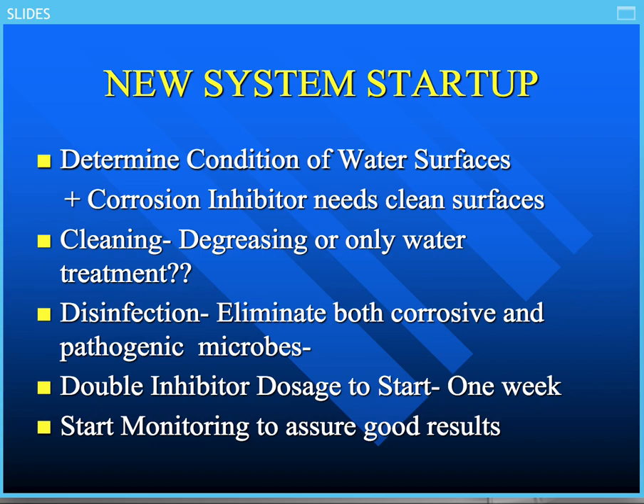The key again is start your monitoring as soon as you start up the system. Don't wait until things get uniform. And when a new system starts up, it doesn't have much load. Because it doesn't have much load, what happens? The water is not evaporating as much in the cooling tower, so you have perhaps a much more corrosive water condition. So you've got to adjust your inhibitor. If that monitoring says I have corrosion rates that are a little bit on the high side, then I better get my inhibitor up there to make sure I'm stopping that corrosion.